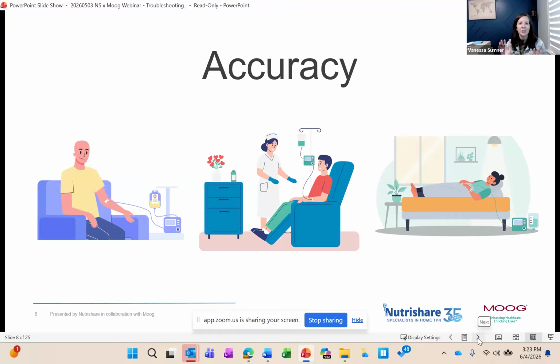If the pump is calibrated to a head height of 12 inches, that means when you place the infusion bag about 12 inches above the pump, the infusion will deliver more closely to the programmed rate. If you look at the slides, the middle picture shows the bag and pump about 12 inches apart. Now, if the bag was way up high, you might get an over delivery. But if the bag and pump are down low, you might get an under delivery.